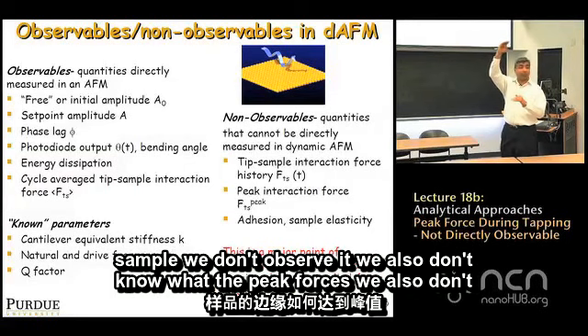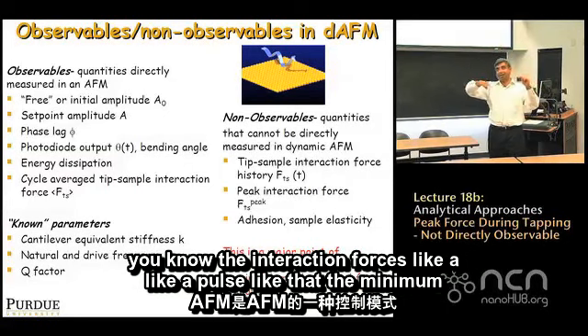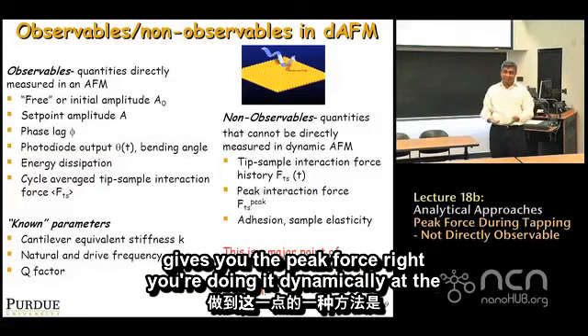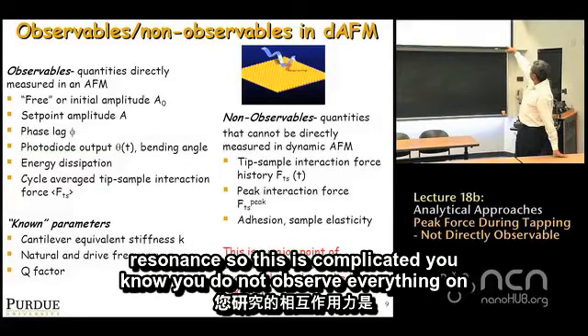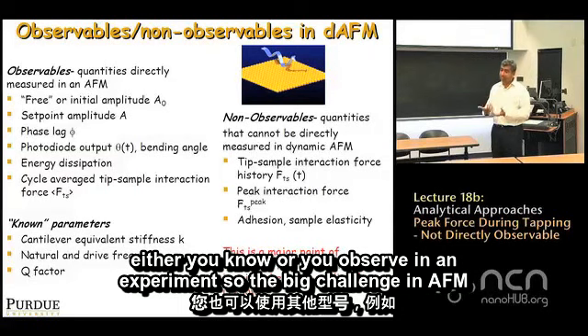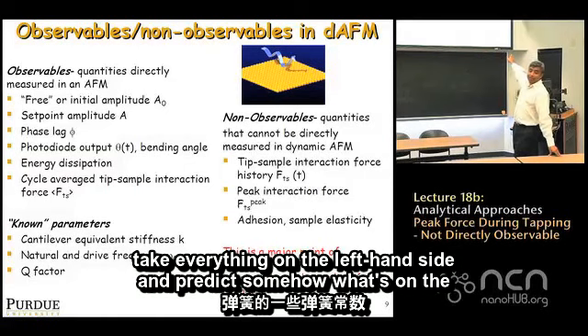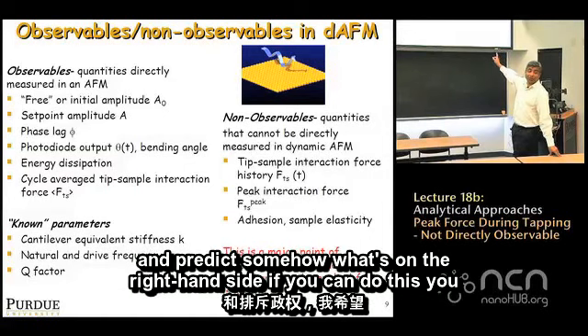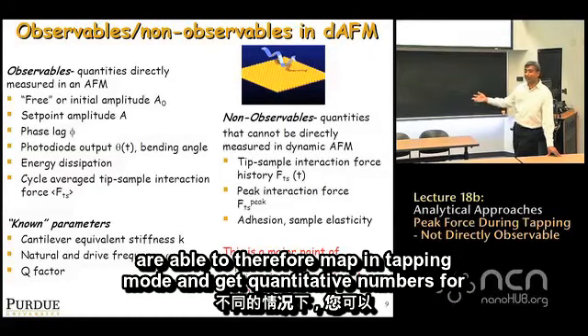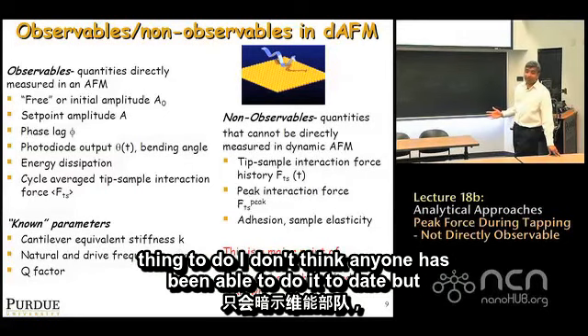We don't observe the peak force or the minimum force. The interaction force is like a pulse — the minimum value gives you the adhesion, the maximum gives you the peak force. You do not observe everything on the right-hand side. The big challenge in AFM for a very long time was how to take everything on the left-hand side and predict what's on the right — to map in tapping mode and get quantitative numbers for adhesion or elastic modulus.